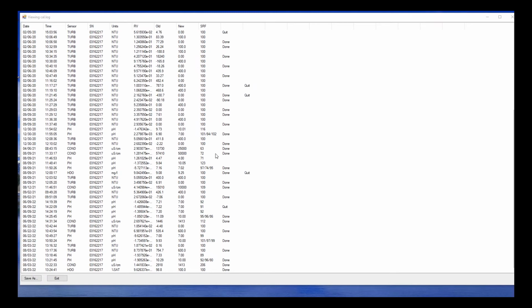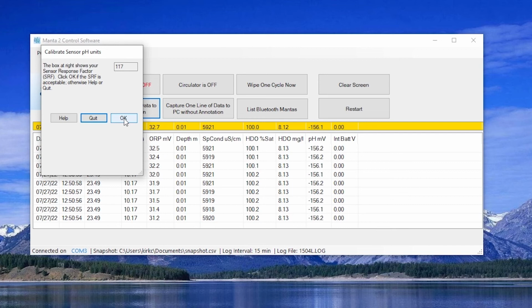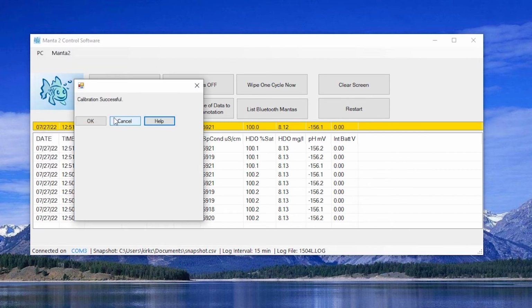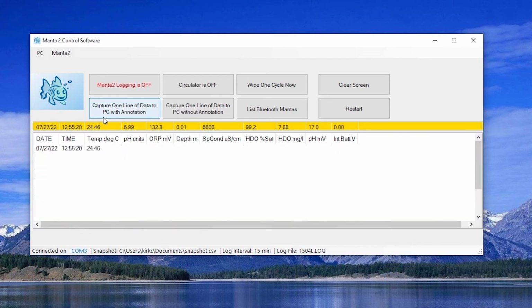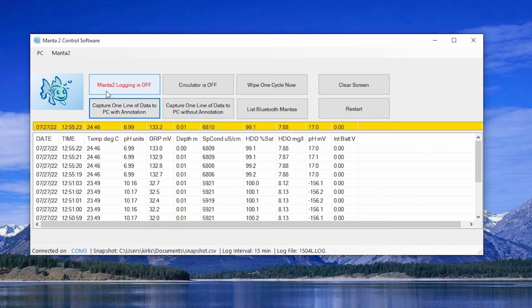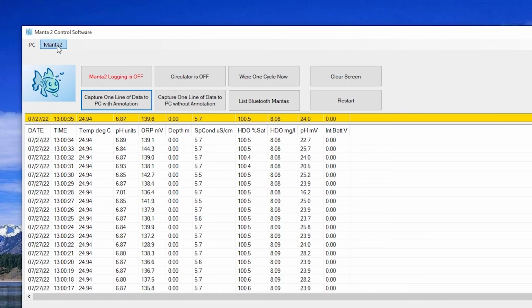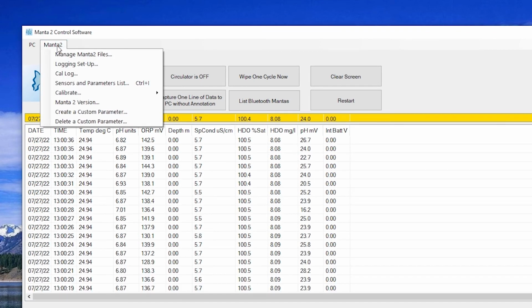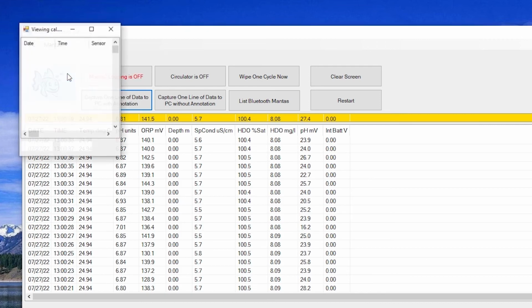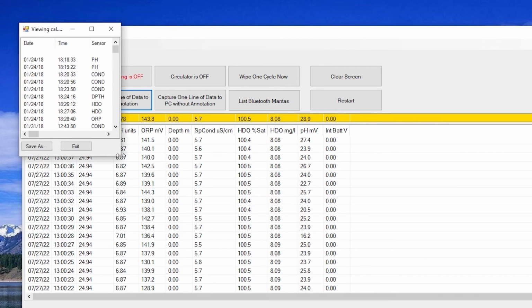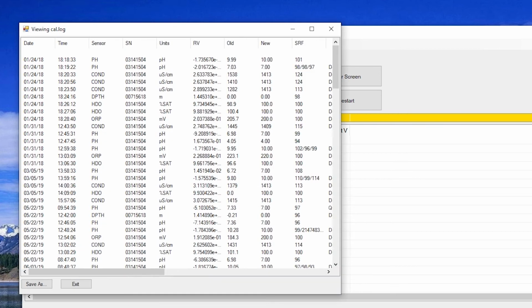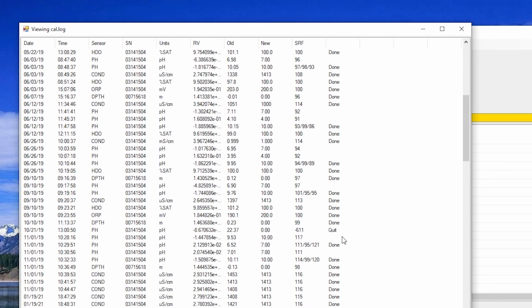If you are not satisfied with your SRF scores, click Cancel to return to the main screen with no changes made to your pH calibration. If you are satisfied with your SRF scores, click OK. For a few seconds, you will see a confirmation that your calibration is successful, then you return to the main screen. Note that your calibration has been stored in the Manta's permanent calibration log, which you can see by clicking the Manta 2 pull-down, choosing Cal Log, and all of the information from any previous sensor calibrations are stored there.